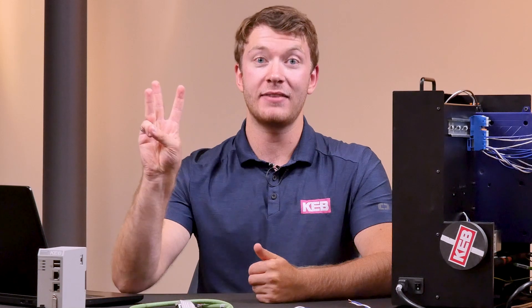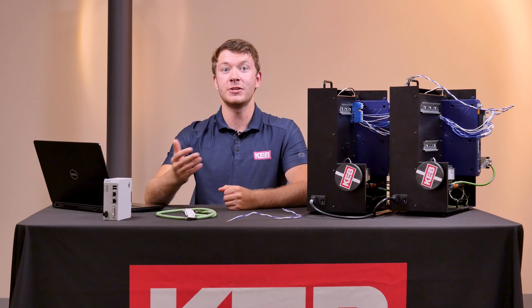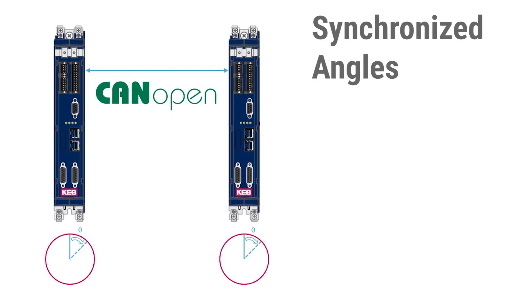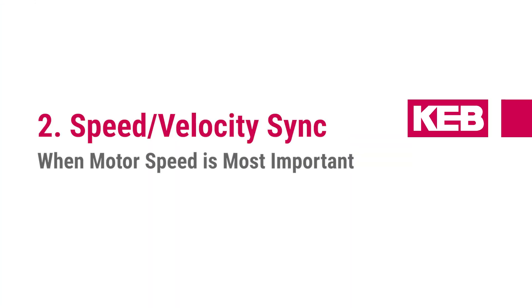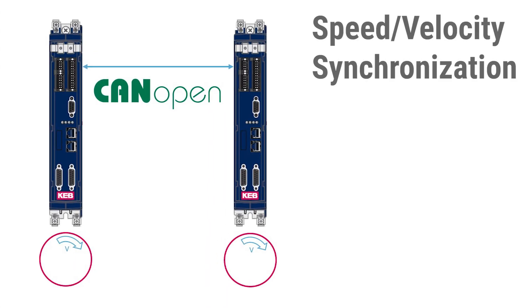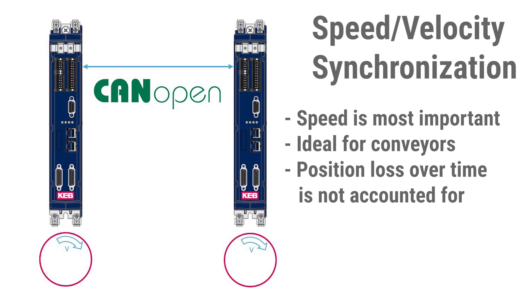CAN cross-communication enables three types of master-follower. The first is angular synchronization, where the position set points of the drives are synchronized together — the actual position of the master drive is transmitted to the follower drive as a set point position. This is important for applications like winders. The second type is speed synchronization, where the speed set point of the master drive is transmitted to the follower as a speed set point. This is critical for applications like conveyors, though position lost over time is not accounted for with this type of control.